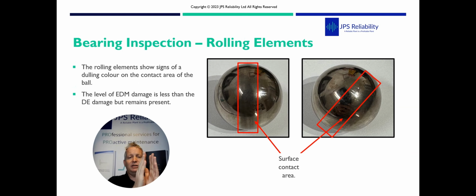These are the bearings. You can see little bands, those grey bands as it's going around. It's the surface contact and it's discharging. So you can see it's a classic EDM failure. The question now is how to prevent it. How do you stop this happening again?